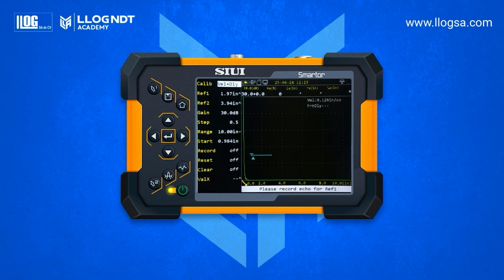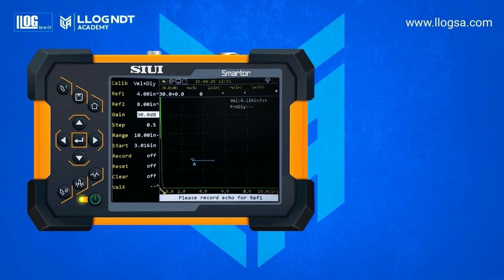In the Auto Calibration submenu, we select Velocity plus Probe Delay Calibration. Reference 1, 4 inches. Reference 2, 8 inches. Now we are ready to perform the angle beam calibration. According to the reference code to be used, some requirements will be necessary for the calibration, which we will describe below. AWS D1.1 calibration requires verification of the index point, distance calibration, angle verification, and sensitivity calibration.